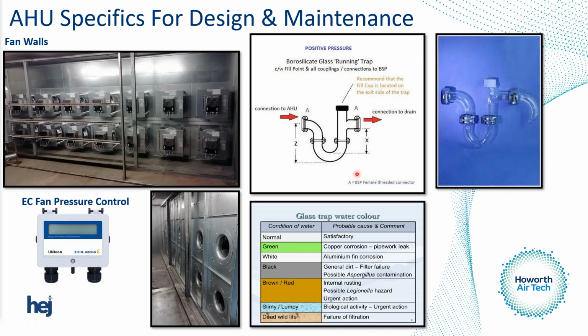It's got a glass trap, you'll have seen them on your sites and designs. The reason I put it here from a validation point of view is because they're directional and have to go a certain way. This side of the trap goes to a copper drain at a certain slant, and there's got to be a 15 mil air gap. These are the things we check to make sure are in position.